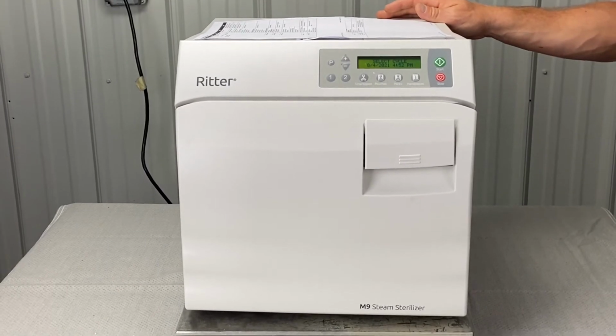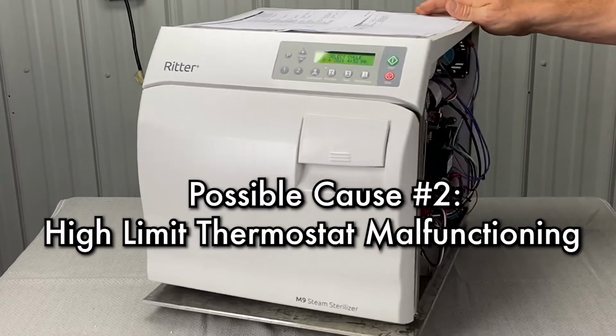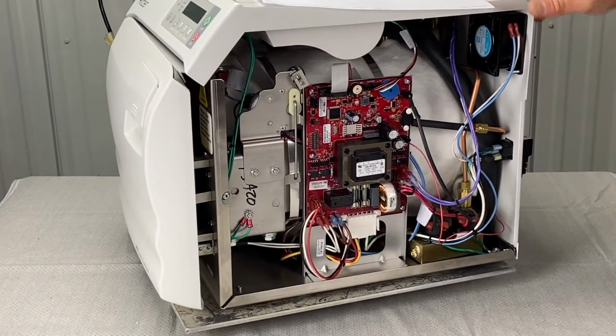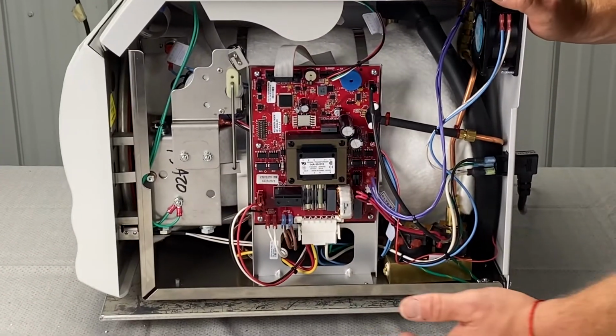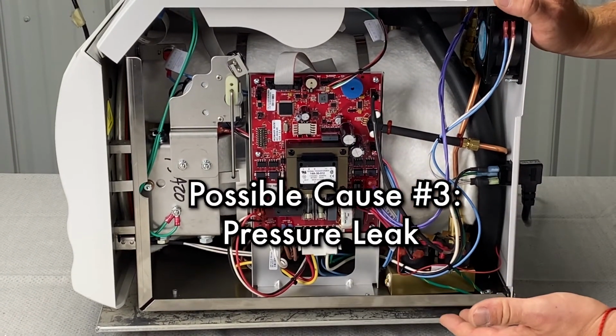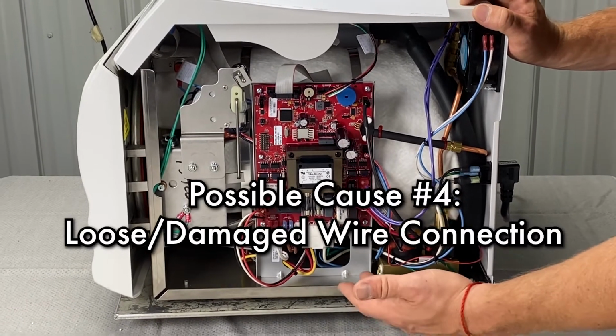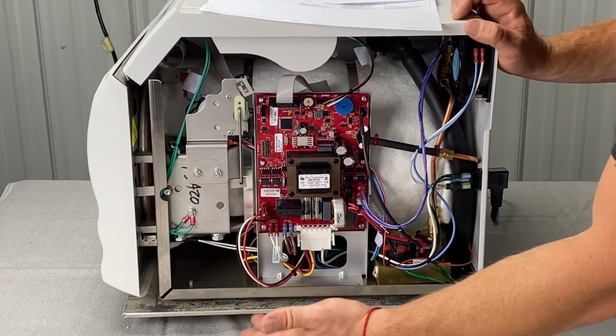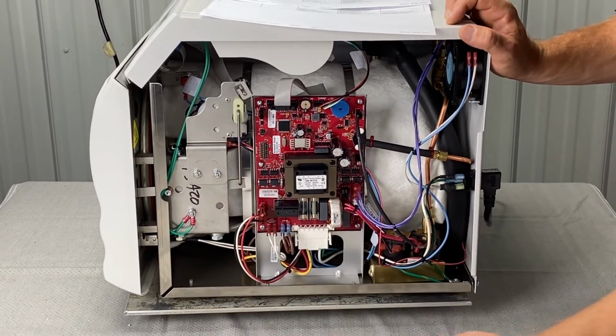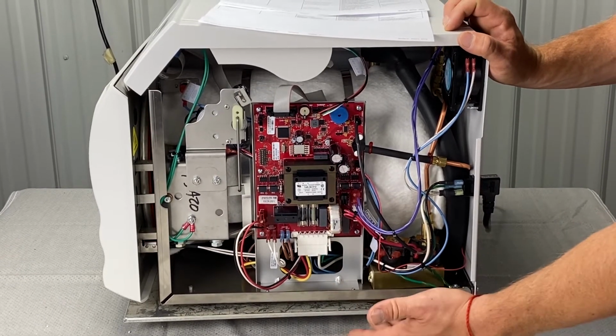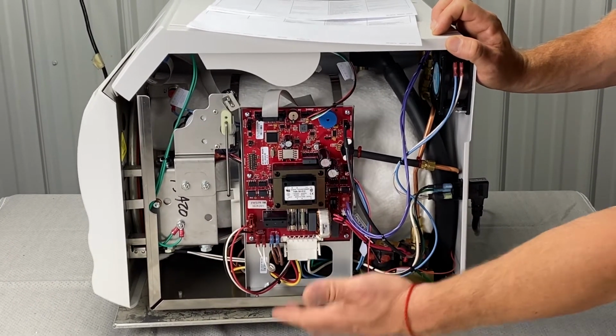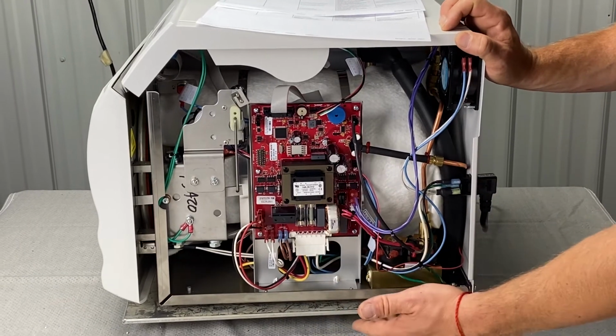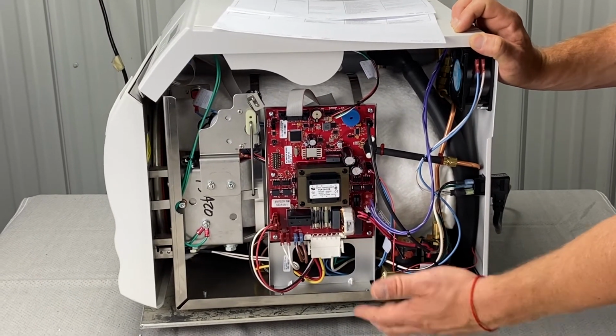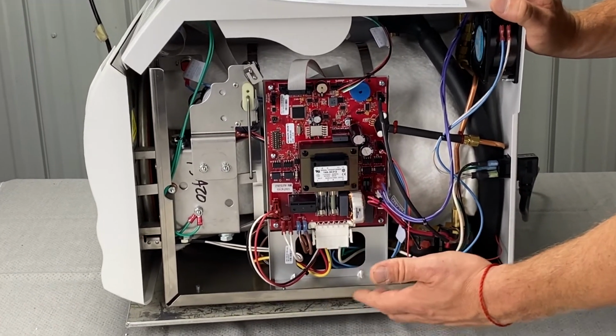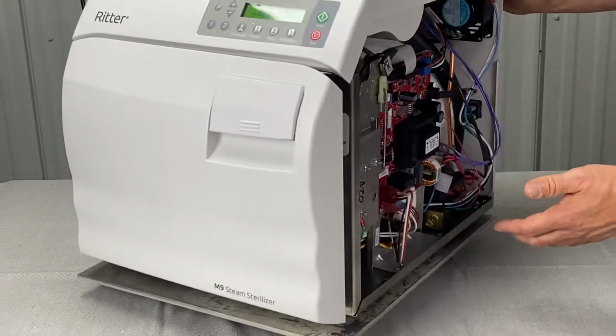Okay, so it is a high limit thermostat issue. The high limit thermostats are underneath the chamber. It could be a pressure leak on this unit. It could be burnt wiring. So we're going to do a lot of things at once. We're going to look underneath the chamber. We're going to look for burnt wiring. If you see that, then we're going to have to fix that before we move to the next phase. But if you don't see any burnt wiring, then we are going to look for leaks, pressure leaks.